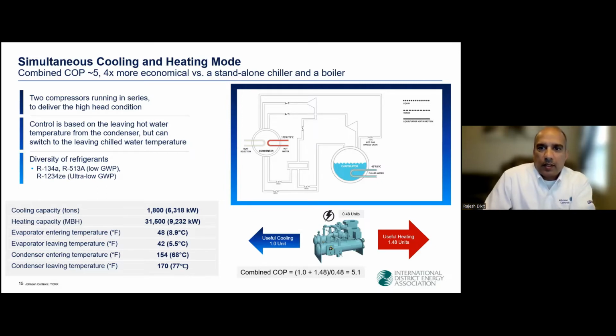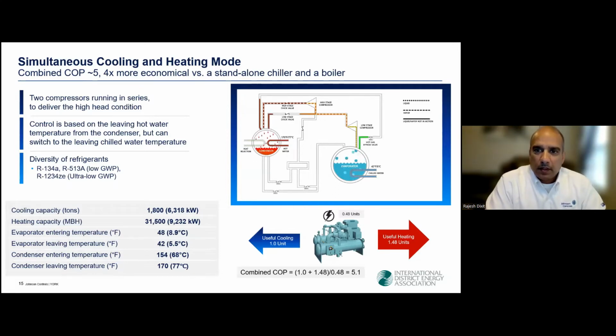So Kit, let's go ahead and play the animation, please. Thank you. Our evaporator is a shell and tube type. Chilled water flows inside the tubes. This is our source, as Kit mentioned in his previous slide. Uniform distribution of suitable refrigerant takes place over the entire set of tubes, as you can see in the animation, due to which the unit produces chilled water, which is used for beneficial cooling. Mesh eliminators or baffles prevent the liquid refrigerant carryover into the compressor.